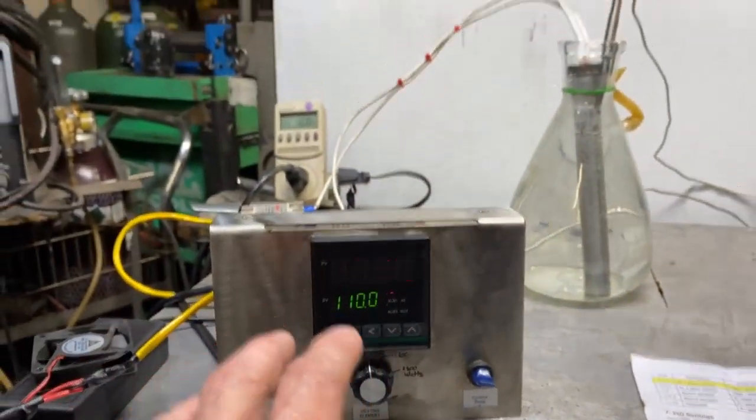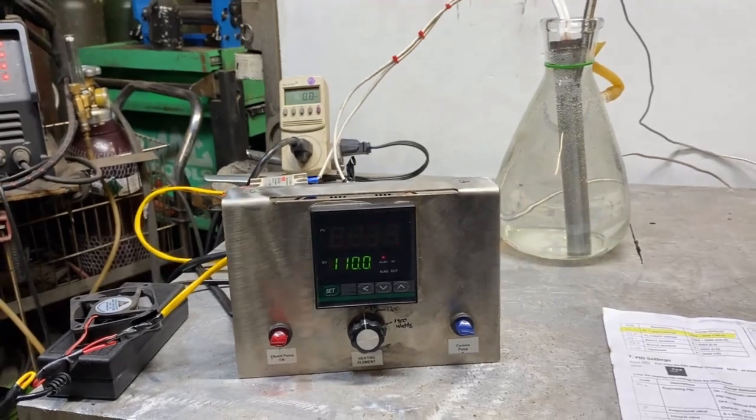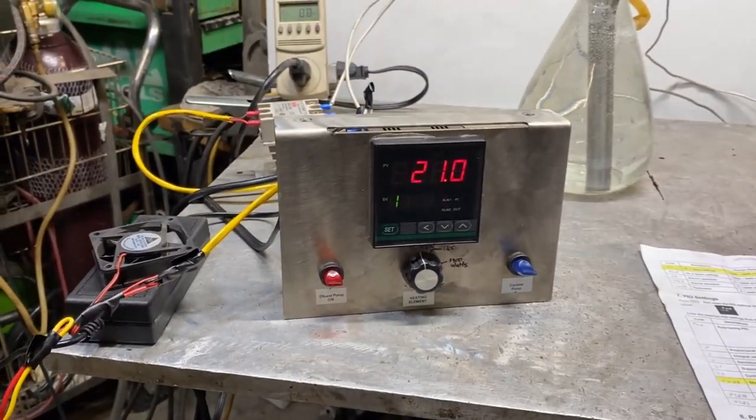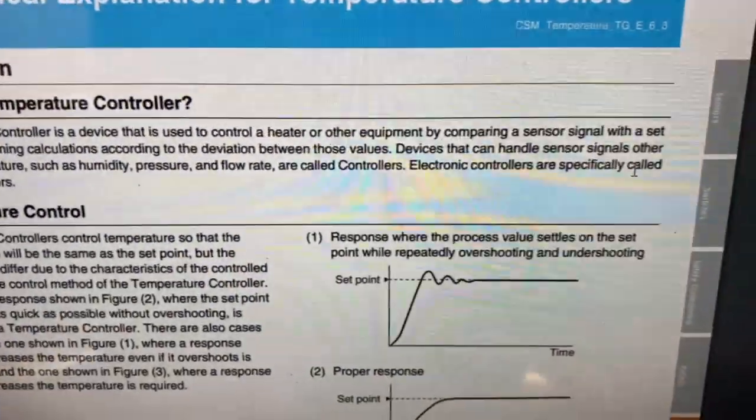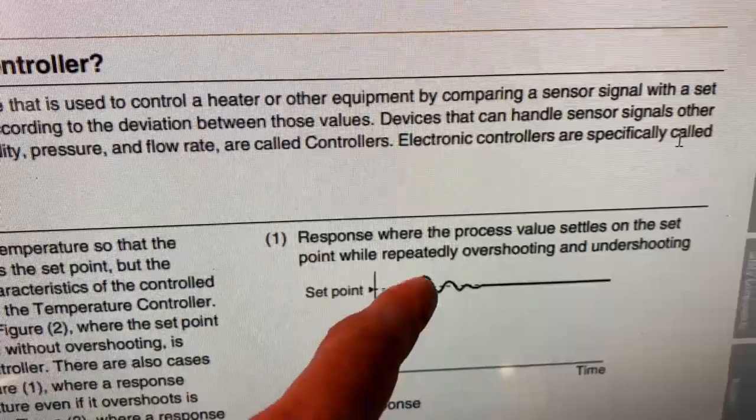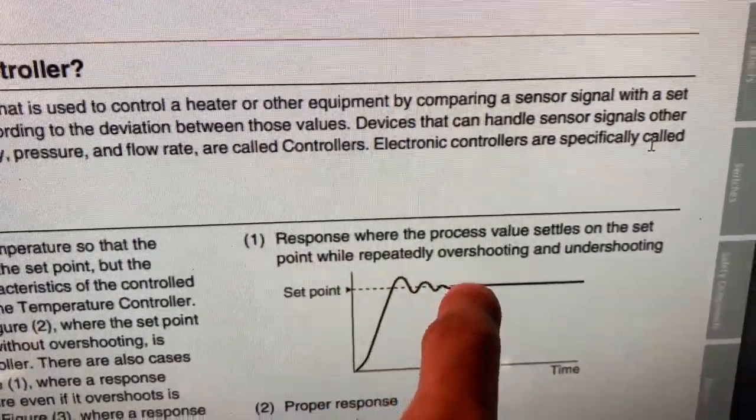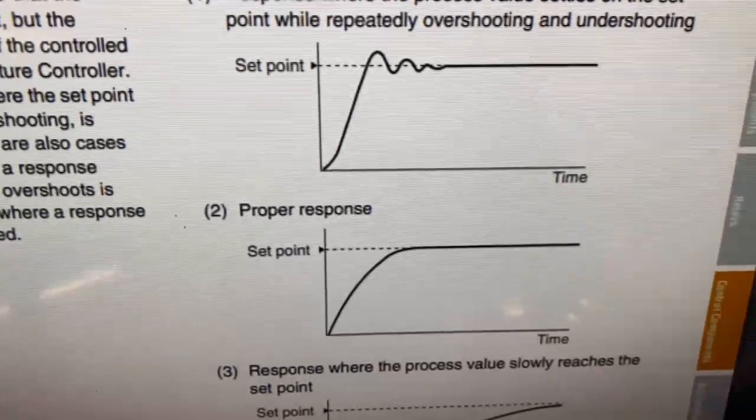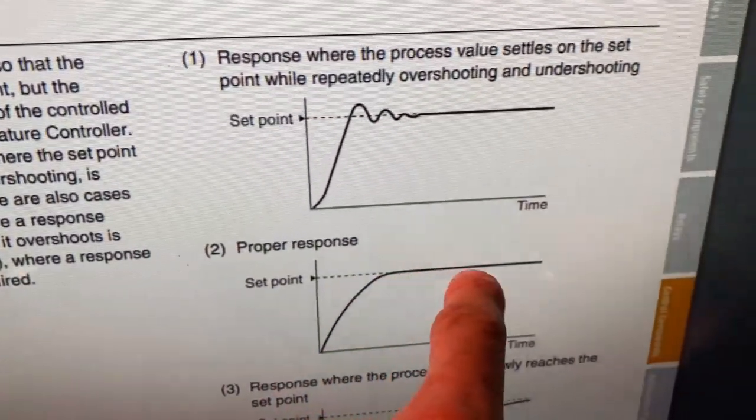You may find that a simple on-off circuit is insufficient for you if the temperature swings are too great in some areas inside the autoclave. If you have it shut off completely, it kind of does this here. It'll go on and overshoot the temp a little bit maybe and then undershoot, overshoot, and it cycles out and eventually it can get you set up. If you have those other adjustments on, it can slowly bring the temperature up and land you where you want to be. If you have them misconfigured, it can take too long.